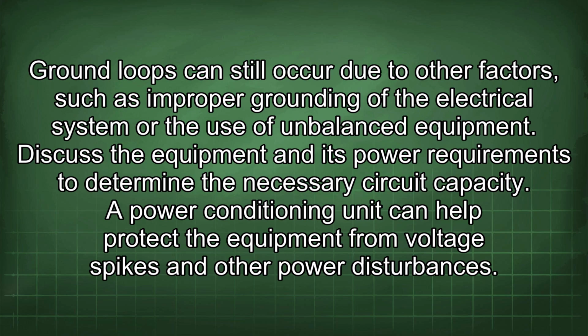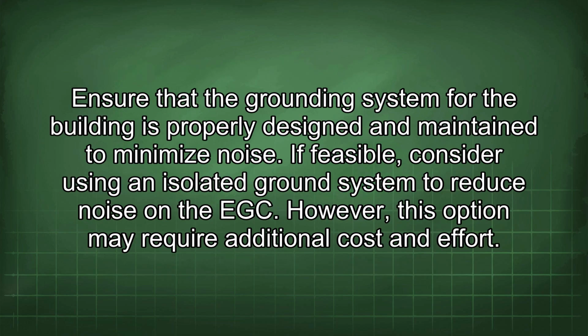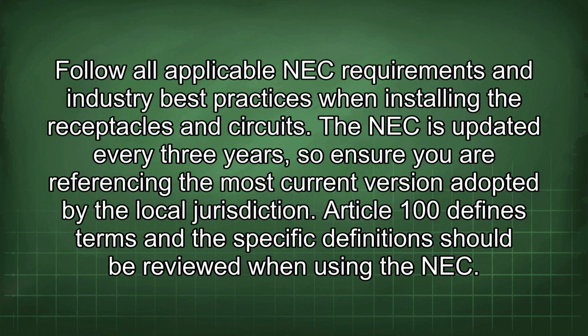A power conditioning unit can help protect the equipment from voltage spikes and other power disturbances. Ensure that the grounding system for the building is properly designed and maintained to minimize noise. If feasible, consider using an isolated ground system to reduce noise on the EGC. However, this option may require additional cost and effort. Follow all applicable NEC requirements and industry best practices when installing the receptacles and circuits.